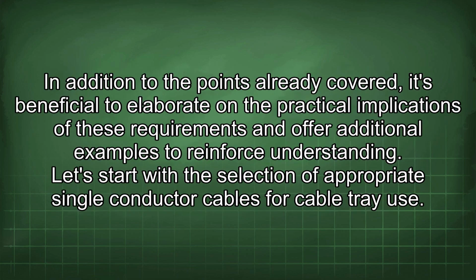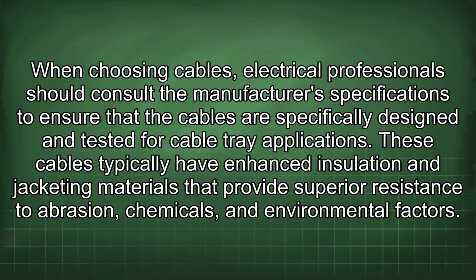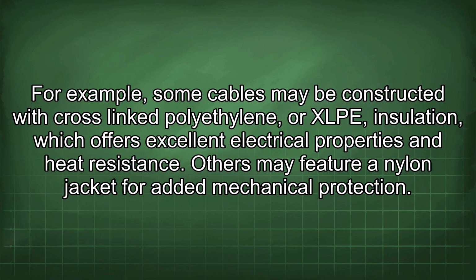In addition to the points already covered, it's beneficial to elaborate on the practical implications of these requirements and offer additional examples to reinforce understanding. Let's start with the selection of appropriate single conductor cables for cable tray use. When choosing cables, electrical professionals should consult the manufacturer's specifications to ensure that the cables are specifically designed and tested for cable tray applications. These cables typically have enhanced insulation and jacketing materials that provide superior resistance to abrasion, chemicals, and environmental factors. For example, some cables may be constructed with cross-linked polyethylene or XLPE insulation, which offers excellent electrical properties and heat resistance. Others may feature a nylon jacket for added mechanical protection.